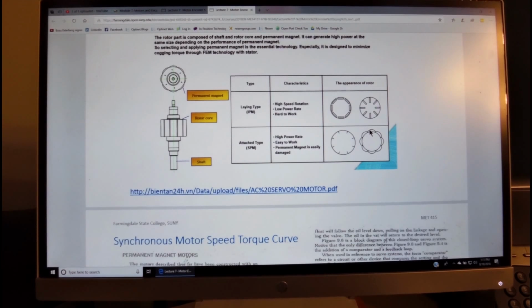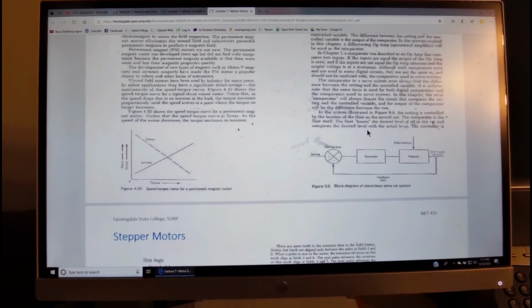And with the shape of the magnets, you see that the magnets may take various shapes, not necessarily sharp edges. That is done in order to reduce the so-called cogging disturbance, where the magnets of the core hit the lamination, which are steel slats for the winding, and generate a shock. So to attenuate the shock and reduce this impact, these magnets get various smooth shapes.